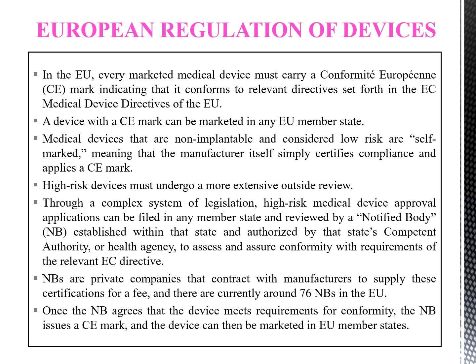A notified body, or NB, is a body established within that state and authorized by that state's competent authority or health agency to assess and assure conformity with the requirements of the relevant EC directive. Notified bodies are private companies that contract with manufacturers to supply these certifications for a fee, and there are currently around 76 NBs in the EU. Once the NB agrees that a device meets the requirements for conformity, the NB issues a CE mark, and the device can be marketed in the EU member states.